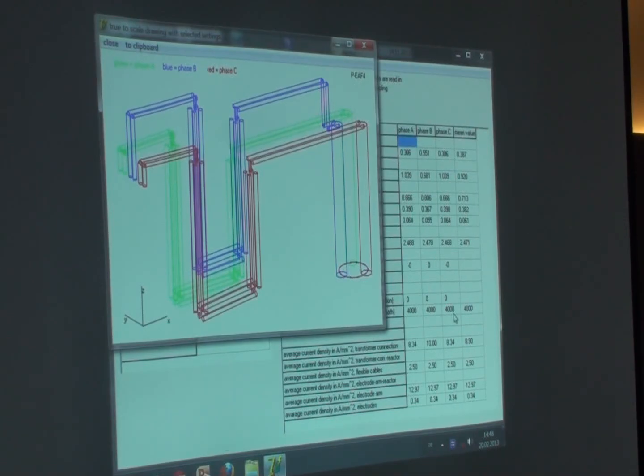These are measured arc voltages and arc currents in a furnace. There's a harmonic amplitude variation of the voltage between 400 volts and 0 — 0 means the electrode hits the scrap — at a frequency of 5 cycles per second, and in the outside phase, half that, 2.5 cycles per second. In phase 1, there's no oscillation.